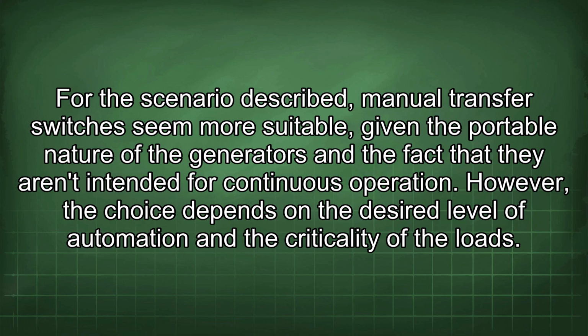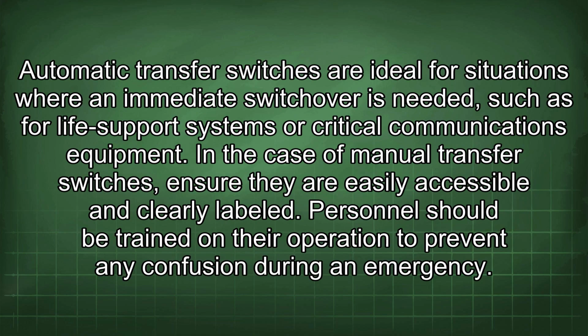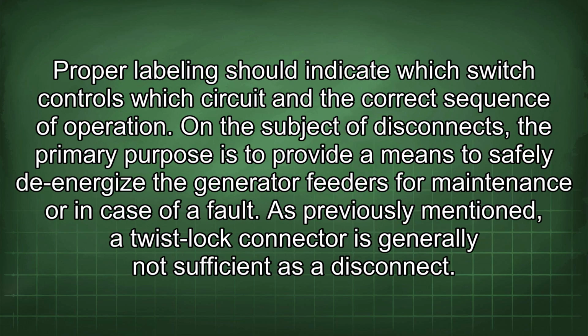However, the choice depends on the desired level of automation and the criticality of the loads. Automatic transfer switches are ideal for situations where an immediate switchover is needed, such as for life support systems or critical communications equipment. In the case of manual transfer switches, ensure they are easily accessible and clearly labeled. Personnel should be trained on their operation to prevent any confusion during an emergency. Proper labeling should indicate which switch controls which circuit and the correct sequence of operation.